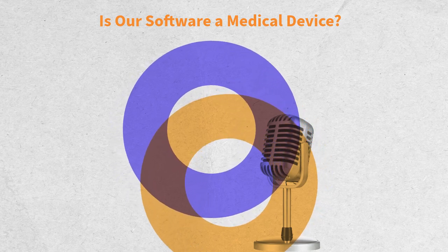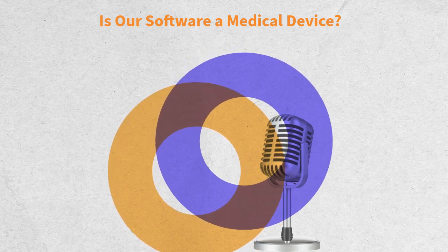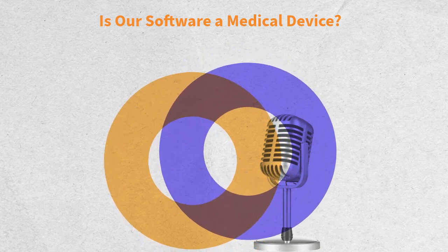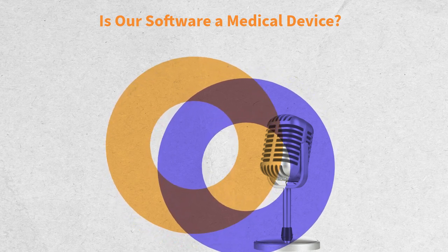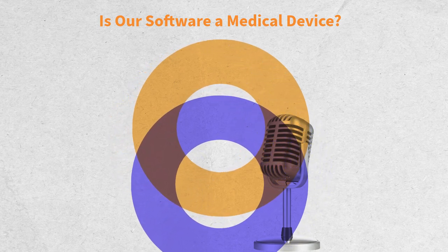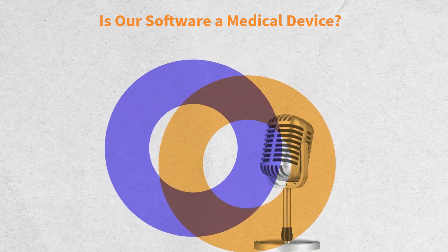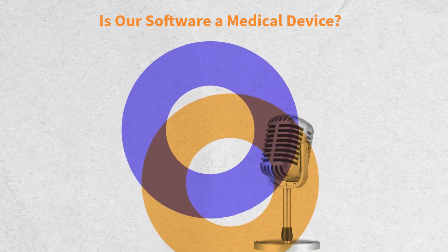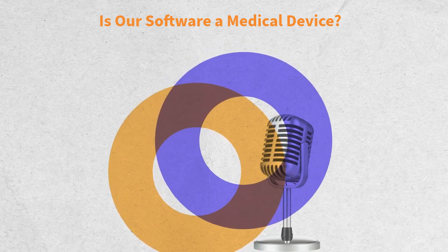An app sending orders to a pump for infusion without processing any clinical value. Still an accessory. A program transmitting collected data with no processing to a central system. It's an accessory, not an MD. If, on the other hand, that algorithm processes data to support diagnosing or clinical monitoring, then it becomes a medical device itself.